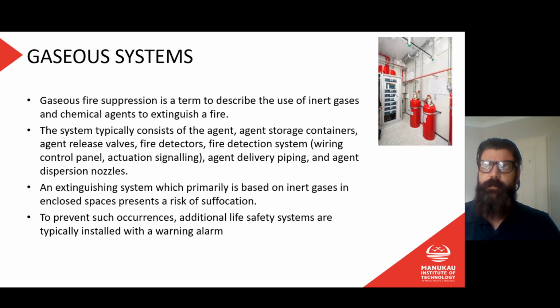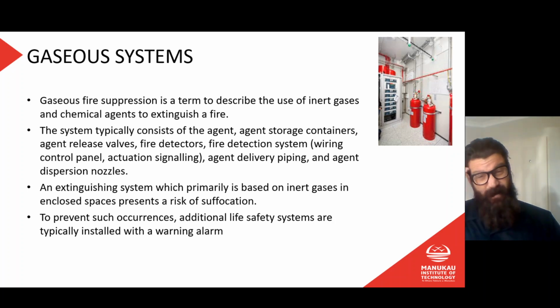One of the big terminals up on the North Shore. I think the one where the Pacific cable comes. There's a big internet cable that comes from America. So there's a big terminal there. It's really expensive. They definitely don't want fire, so they've got a gas system in there, and one of the guys doing the inspections actually set it off, and it costs about $30,000 to get new gas bottles in there. And obviously evacuated the building, and all sorts of horrendous things happened.